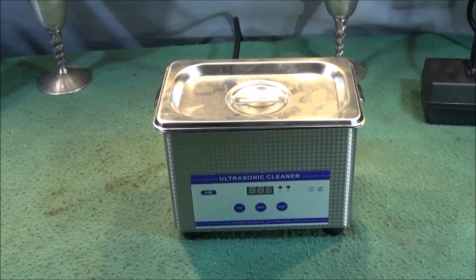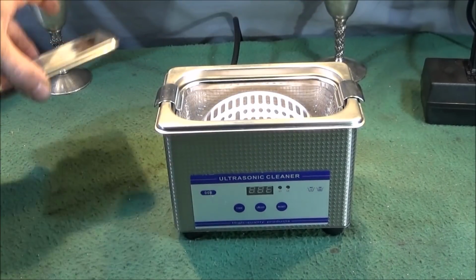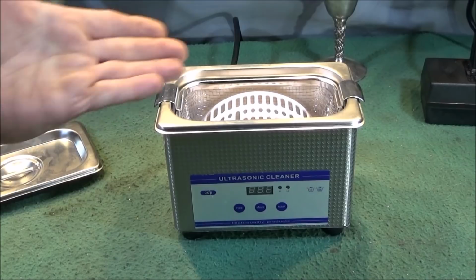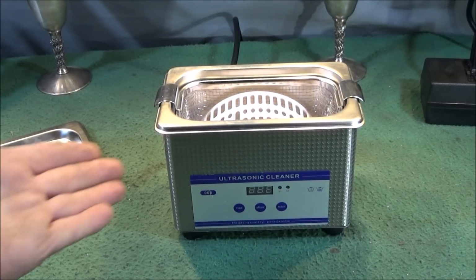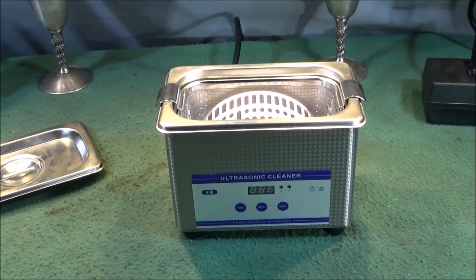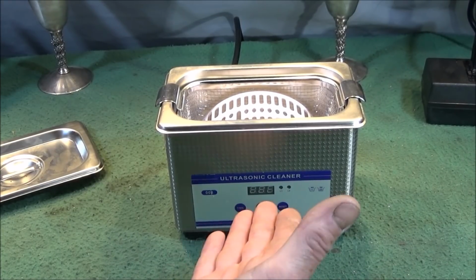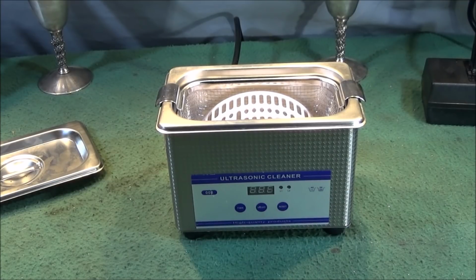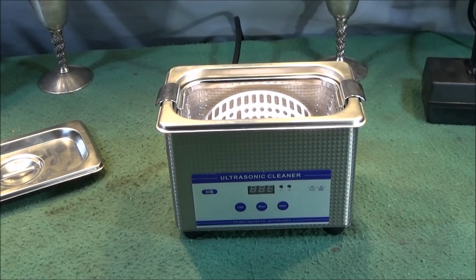Now, the cleaner must not be used or switched on when it's empty or without liquid in it. The instructions say that if you start it up without any liquid, there's a danger of damaging the electronic transducer.